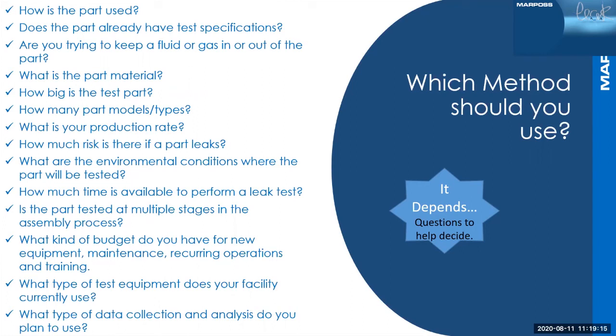Some of the things that you want to look at is, what type of data collection and analysis do you plan to use? If you're looking at a lot of data collection and you want to analyze it, you may want to make sure that linearity is an important factor. There are test methods out there that will give you a go, no-go very accurately, but aren't very linear. So you want to pay attention to that if you're planning to collect data.